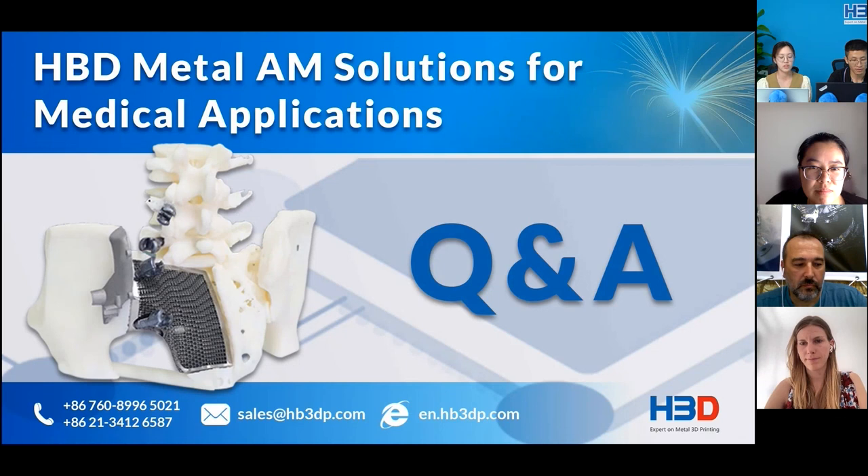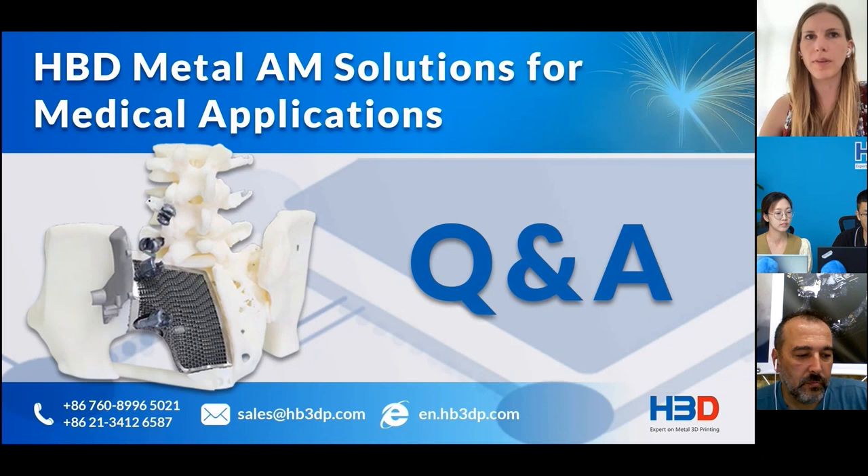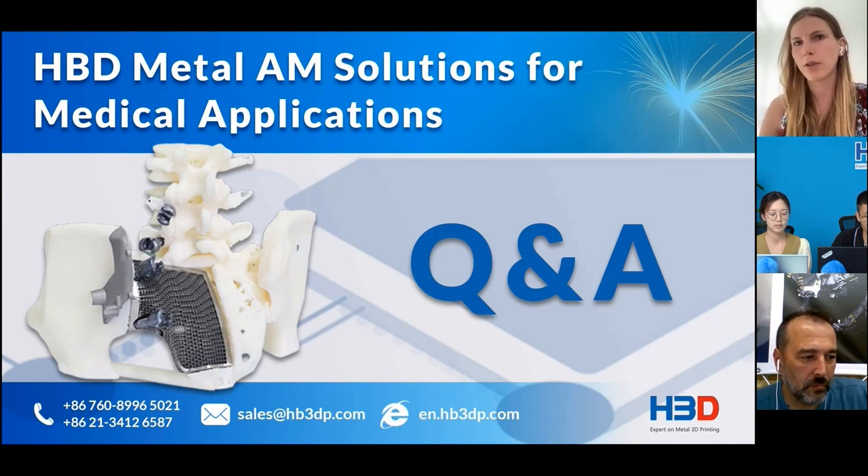I also got a question for Emily: How can an orthopedic implant design workflow be automated using algorithmic engineering? We can encode laborious human-driven engineering processes into computer algorithms to create customized and integrative implant designs for additive manufacturing. We basically automate the whole process from taking patient-specific segmented CT scans to production-ready implants.